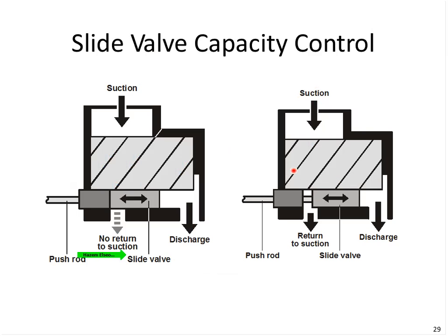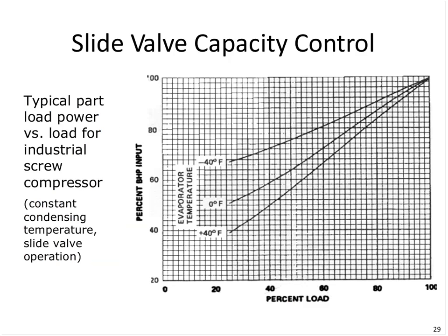Now, the rotor is still turning at a fixed speed, would still have the level of friction, but we just wouldn't have as much compressing. The idea of variable speed then would be to leave the slide valve disengaged and just change the speed of the rotors, and our benefit there is through reduced friction at lower speeds.